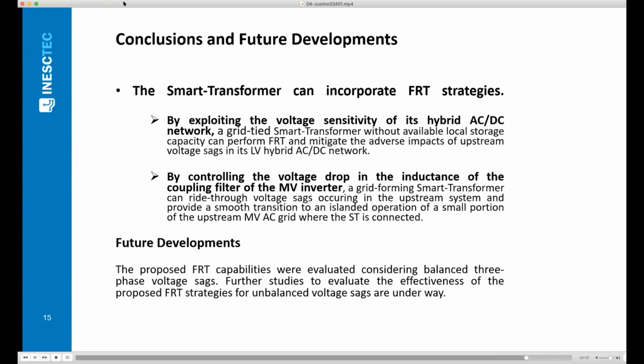By exploiting the voltage sensitivity of its hybrid AC-DC network, a grid-tied smart transformer without available local storage capacity can perform fault ride-through and mitigate the adverse impacts of upstream voltage sags in its low-voltage hybrid AC-DC network. Also, by controlling the voltage drop in the inductance of the coupling filter of the medium voltage inverter, a grid-forming smart transformer can ride through voltage sags occurring in the upstream system and provide a smooth transition to an islanded operation of a small portion of the upstream medium voltage AC grid where the smart transformer is connected.